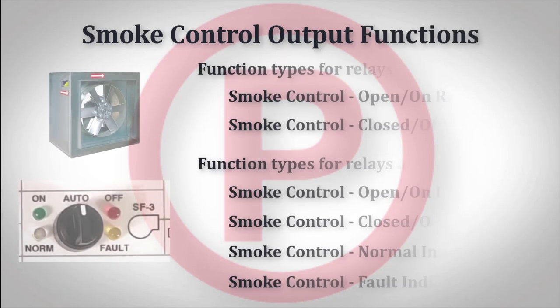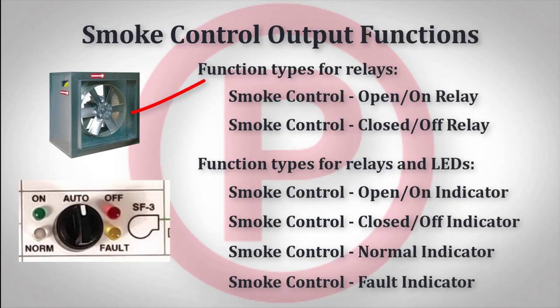The smoke control output function types are as follows: smoke control open or on and closed off relays for controlling the fans or dampers; smoke control open or on, closed or off, normal, and fault indicators to illuminate the LEDs on the firefighter's smoke control station.